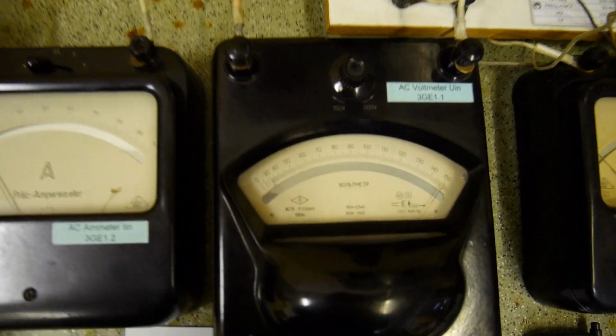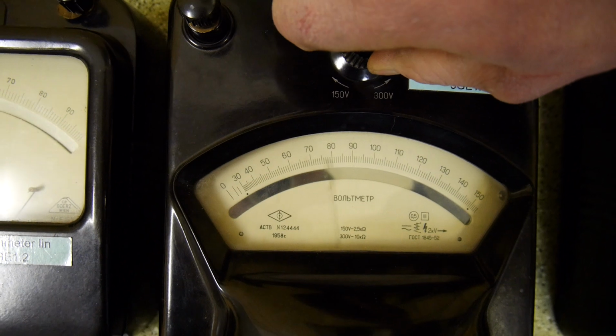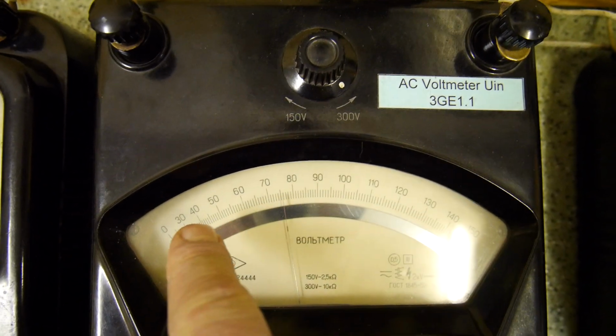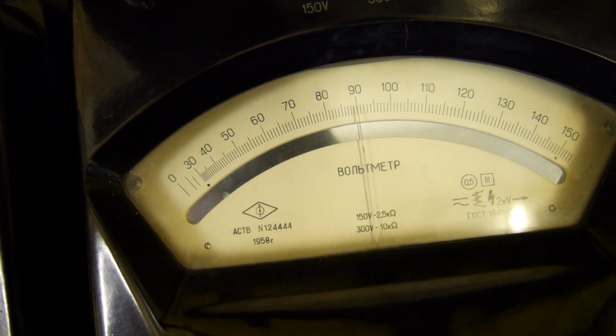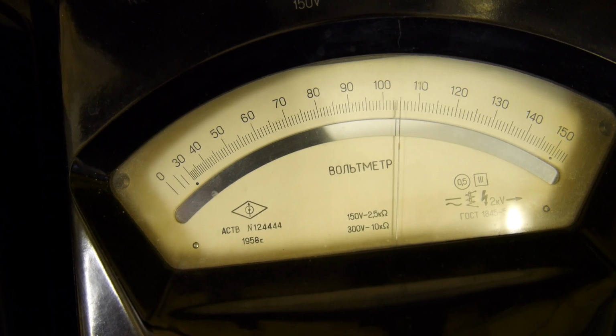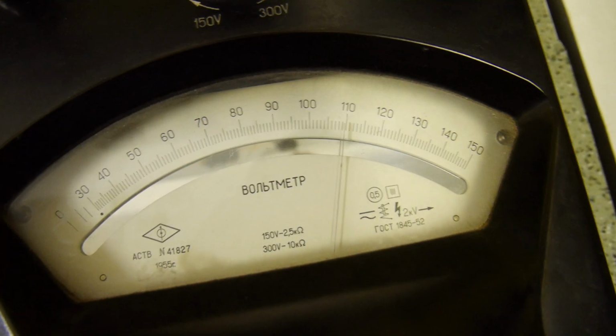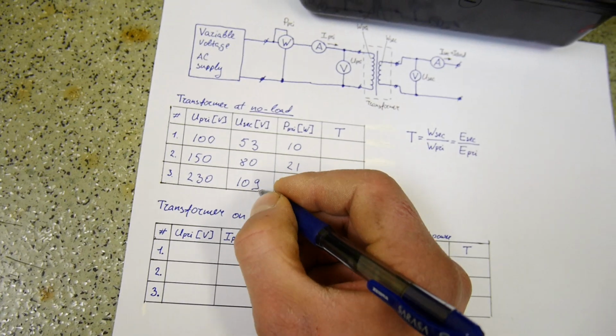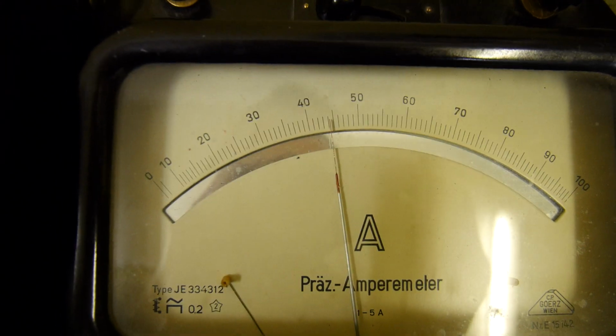Finally, let's go to the rated voltage. The rated voltage is 230 volts, so I have to switch the range to 300, so now the full scale range is 300. So 230 volts. The secondary voltage increases too. The secondary voltage now is approximately 108. The primary current also is rising, but the consumed power is still very small, approximately 26 watts.